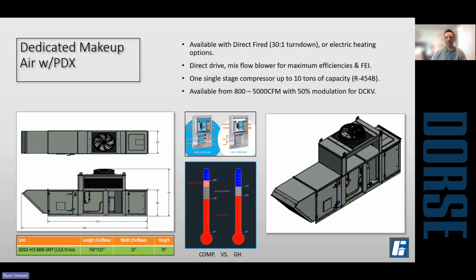This one is designed for sensible heating and cooling. So again, we're going to turn on the heat below 60 and turn on cooling above 75. And there in the center is an example of how they're able to accomplish the 50% reduction in airflow. It's utilizing a face and bypass damper. So when they go to the 50% airflow, they close that damper, forcing all the air across the burner so they maintain a good differential pressure and a nice clean burn.